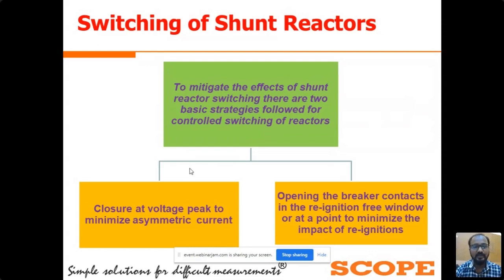We have the reference of system voltage, and we all know there is a 90-degree phase shift between the voltage and current for the inductive load. So we know that whenever the voltage is at peak, the current is at 0. So for the closing of shunt reactor, we are targeting the voltage peak points. We are taking the reference of voltage peak angles.